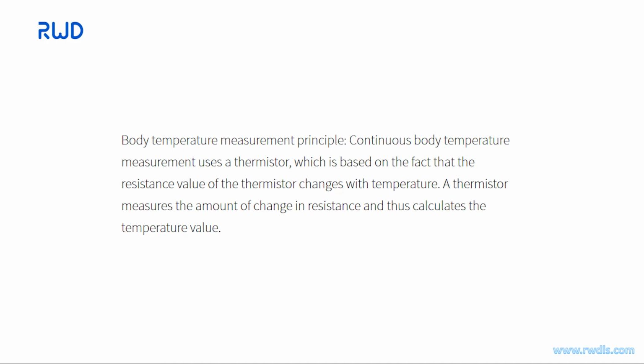Body temperature measurement principle. Continuous body temperature measurement uses a thermistor, which is based on the fact that the resistance value of the thermistor changes with temperature. A thermistor measures the amount of change in resistance and thus calculates the temperature value.